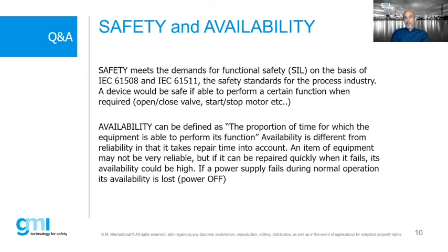Okay. Availability is the proportion of time for which the equipment is able to perform its function. So availability is different from reliability. I would say that reliability is more related to the probability of failure on demand, to the safety, to the SIL level. But availability is very important because if you don't have the function available, you are not able to produce because of failures. It maybe doesn't pose any real risk or problem for people and for the plant, but it stops your system, stops your production, which is also very critical.